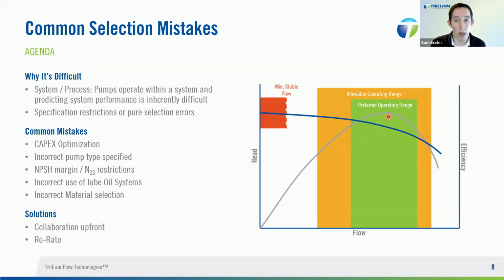And that point for a pump is referred to as BEP, or best efficiency point. And we'll talk about on the next slide why that's so significant. But if you can just imagine it as these typical zones, so you have a green area where it wants to run and it's going to be at its most content. You have an area that the pump manufacturer will say, you can run here, but it's not our advised area. And outside of those is when you're typically going to really start to impact the life of the unit.